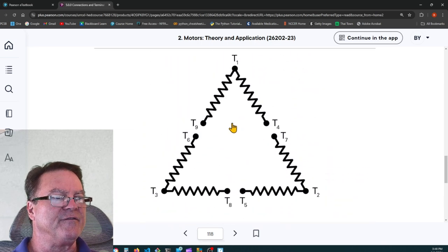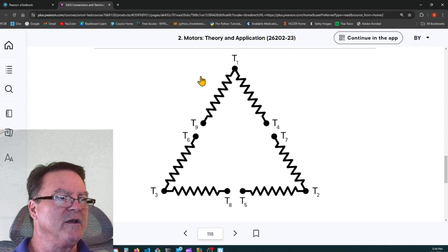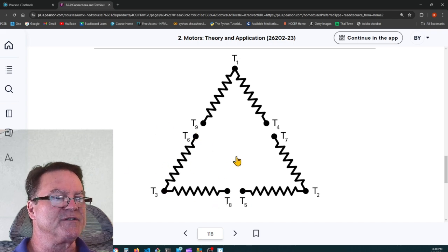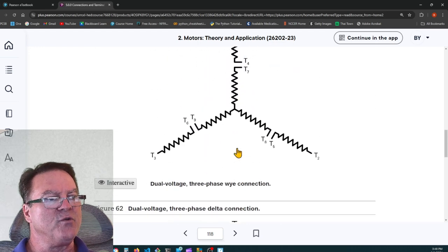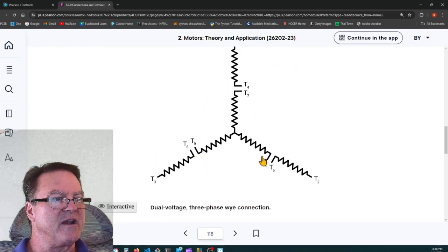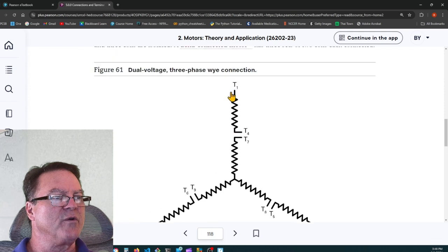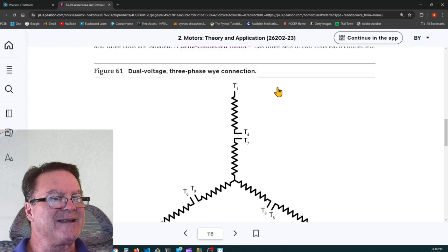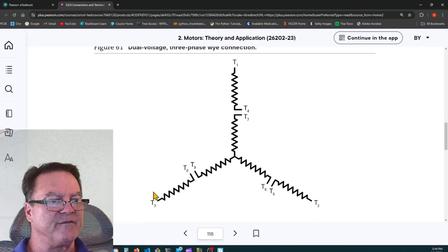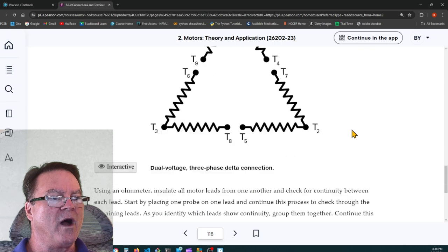So again, if you find continuity between three groups of three. If you have continuity between 4, 9, and 1, that's a group, and 7, 2, and 5, and 8, 3, and 6, then you know that this is a delta motor. If you have continuity between 7, 8, 9, but you don't have continuity, the other three are isolated, you have 1 and 4, 2 and 5, 3 and 6, then you know it's a Y motor.